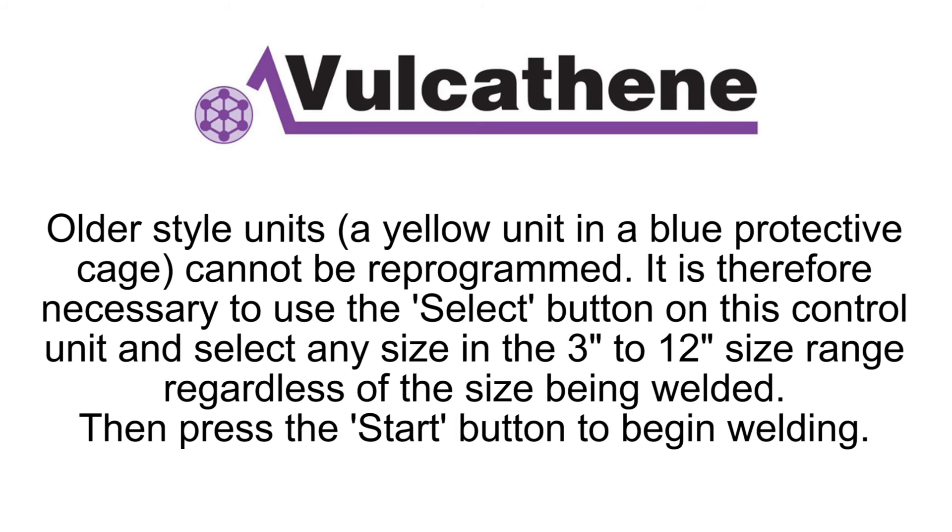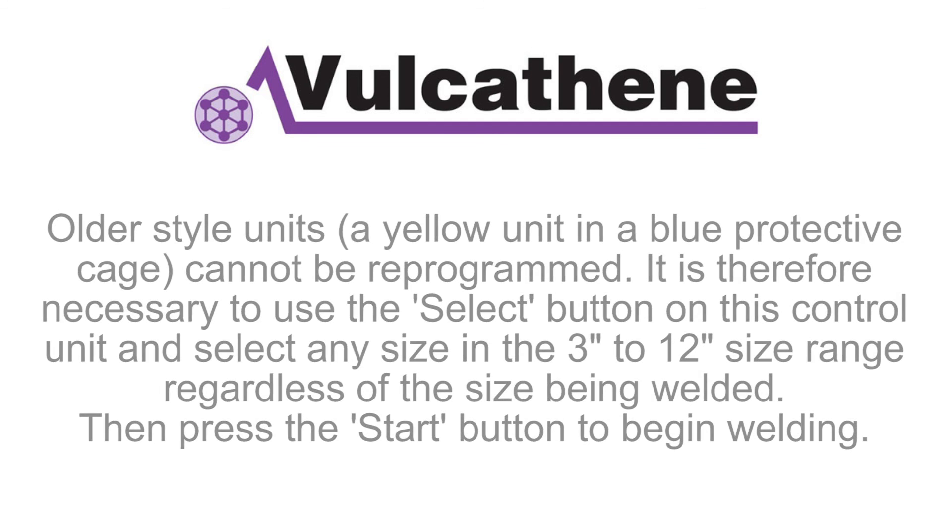Older style units (a yellow unit in a blue protective cage) cannot be reprogrammed. It's therefore necessary to use the select button on this control unit and select any size in the 3 inch to 12 inch size range regardless of the size being welded, then press the start button to begin welding.